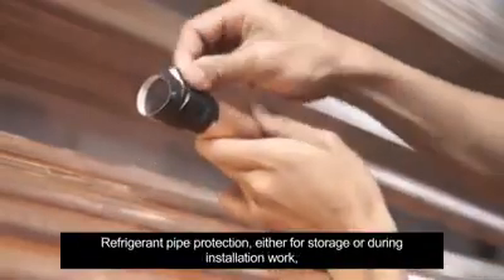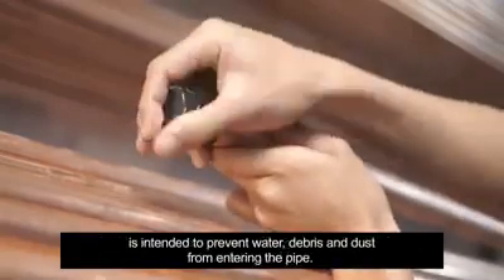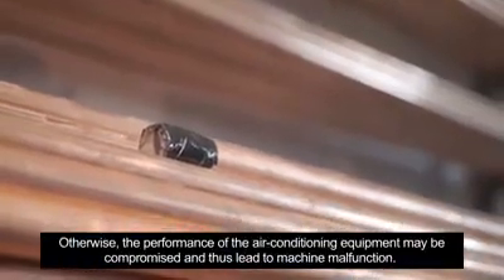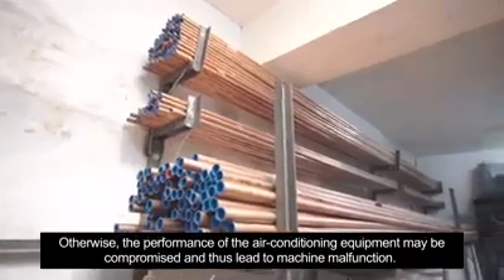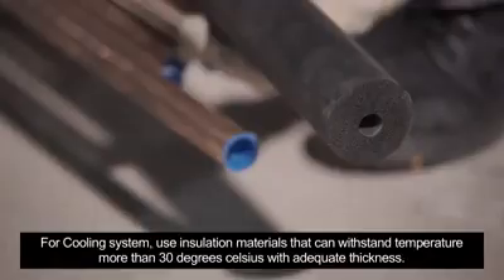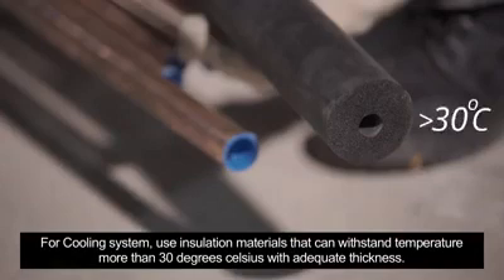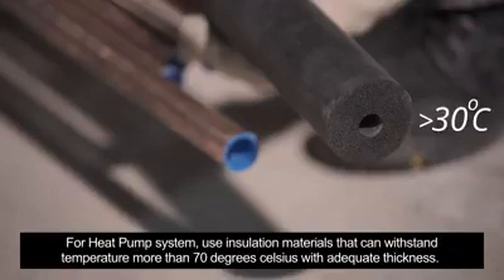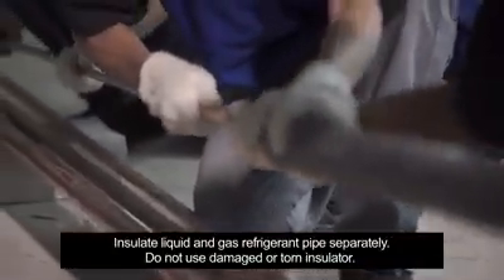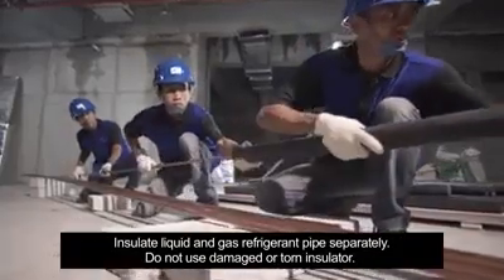Refrigerant pipe protection, either for storage or during installation work, is intended to prevent water, debris and dust from entering the pipe. Otherwise, the performance of the air conditioning equipment may be compromised and thus lead to machine malfunction. For cooling system, use insulation materials that can withstand temperature of more than 30 degrees Celsius with adequate thickness. For heat pump system, use insulation materials that can withstand temperature of more than 70 degrees Celsius with adequate thickness. Insulate liquid and gas refrigerant pipes separately. Do not use damaged or torn insulator.